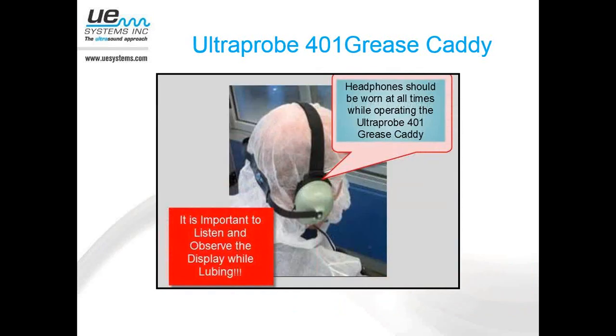And with any of our Ultraprobes, you always want to make sure that you have the headset on at any given time. Some people say, well, I'm watching the decibel level, why do I need to wear the headset? Well, when you're listening to the bearing, you're going to hear if the bearing is in some sort of failure mode. A bearing that has an inner race or outer race fault, or some other kind of fault, is going to sound a lot different than a bearing that just needs to be lubricated. So having that headset on is always going to be important.